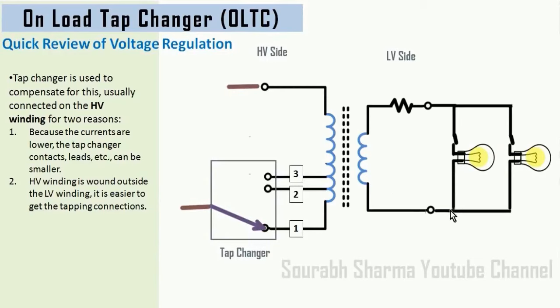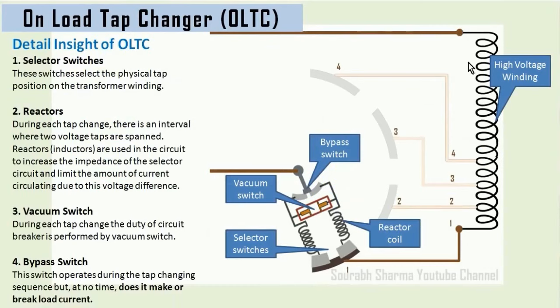The drop in output voltage due to load current is compensated by reducing the number of turns in the HV winding. This improves the per-turn voltage of the HV side, followed by an increase in per-turn voltage of the LV side. This process is continued until the output voltage regains its previous value. Although this process is not easy — the internal structure of OLTC is quite complex. The high voltage winding is shown from which different tappings are brought out: the first tap, the second, the third, and the fourth.